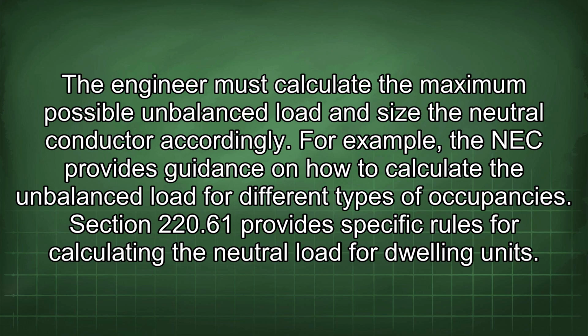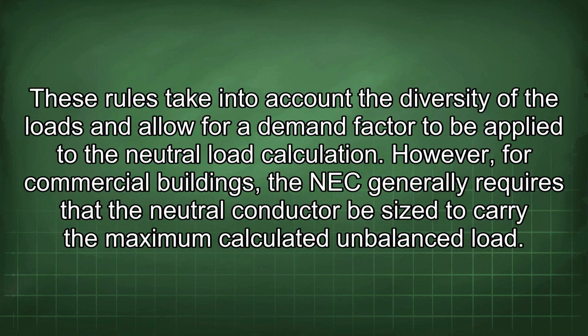Section 220.61 provides specific rules for calculating the neutral load for dwelling units. These rules take into account the diversity of the loads and allow for a demand factor to be applied to the neutral load calculation. However, for commercial buildings, the NEC generally requires that the neutral conductor be sized to carry the maximum calculated unbalanced load.